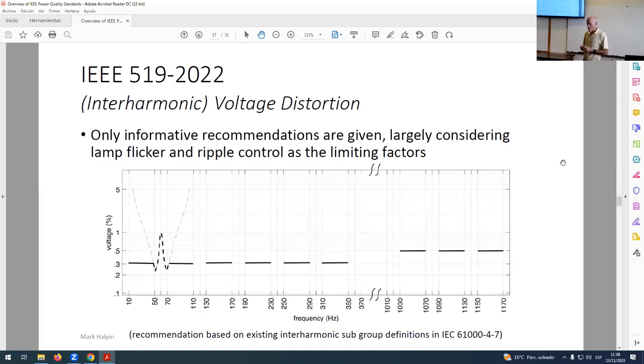No, right? Maybe. In the United States, that might be more true, but a lot of countries, especially countries in Europe and countries like Australia and New Zealand, for sure, use ripple control, okay? Basically, we're using the utility system as a low frequency communication channel, so we had better make sure that we don't allow emissions from some kind of interharmonic to interfere with that. So the initial concept that we're thinking about for interharmonic limits is, around the power frequency, base the limits on light flicker. For higher frequency interharmonics, base the limits on acceptable levels to avoid interference with ripple control.